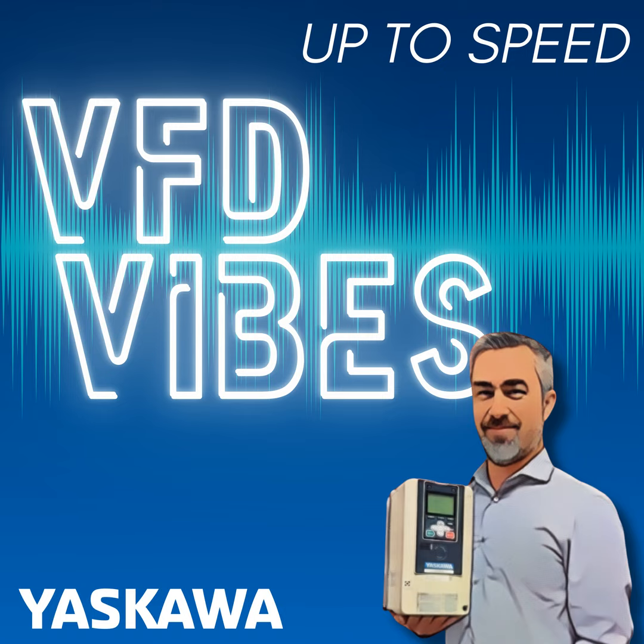Now, the thing I want to caution people on with the use of software is it's an estimation tool. It is not a substitute for an on-site study where you might bring in measurement equipment and measure over the course of 3 or 4 days or a week and then get a full report. So this is an estimation on the front end of purchasing a VFD, so you can have a rough idea of, are harmonics going to be a problem? And if so, you can purchase either the right VFD or the right options at the time of purchase to help mitigate those harmonics.